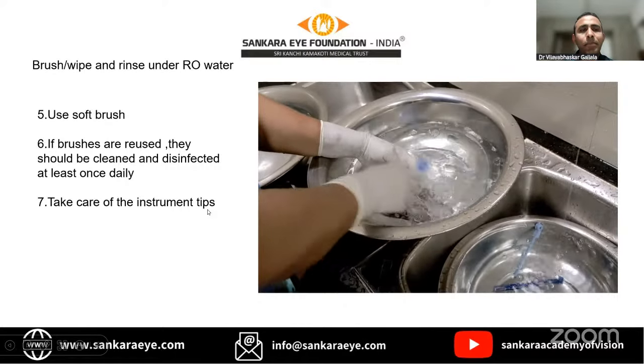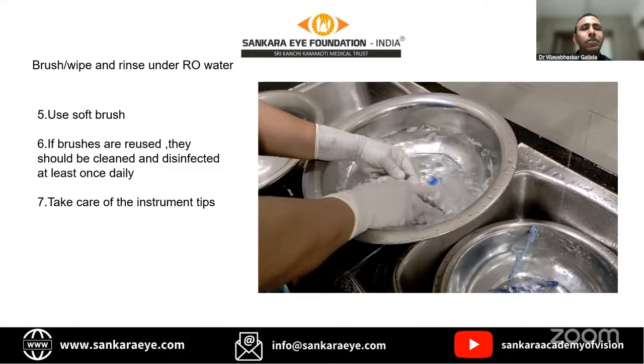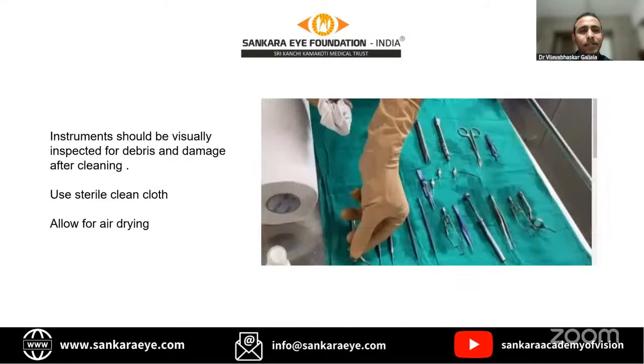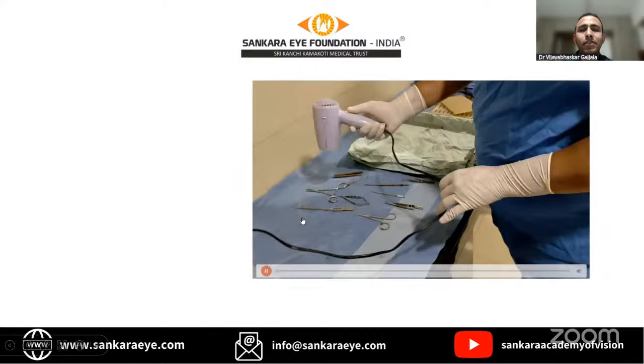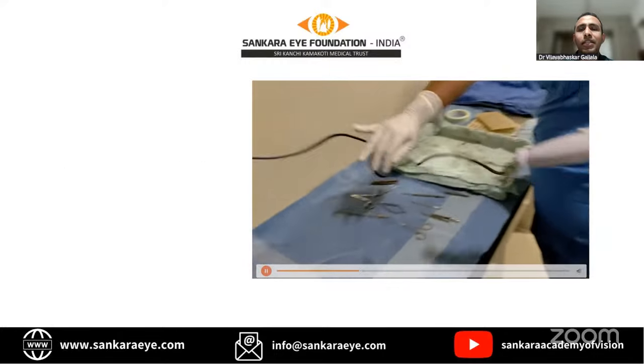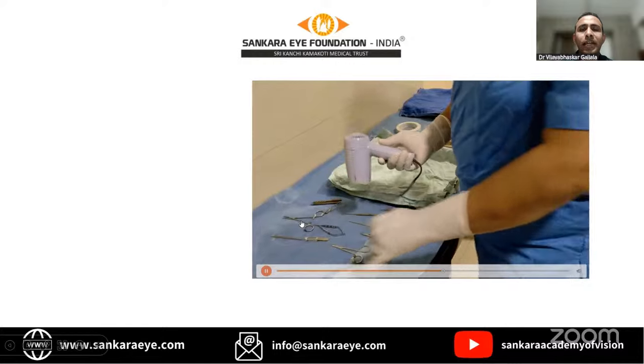If you are using the brush multiple times, make sure you disinfect it at least once daily. Once the cleaning is over, you should keep the instruments and the clean cloth away from that cleaning area, and inspect for any debris or damage after cleaning. If you find any debris, don't hesitate to send it back for further cleaning. Always use a sterile clean cloth, and you can allow these instruments to air dry before preparing the pack. And if you want to prepare the pack fast, you can use a high flow jet air gun to dry very fast.